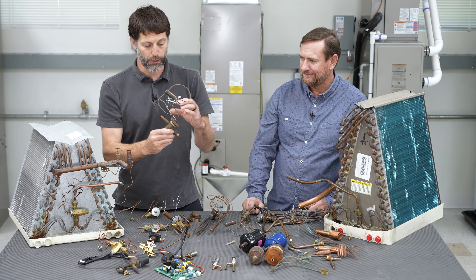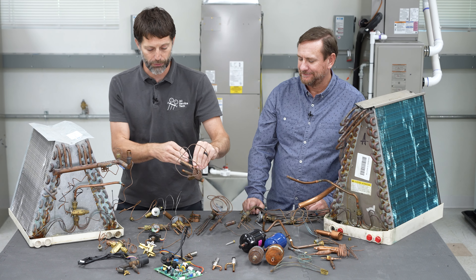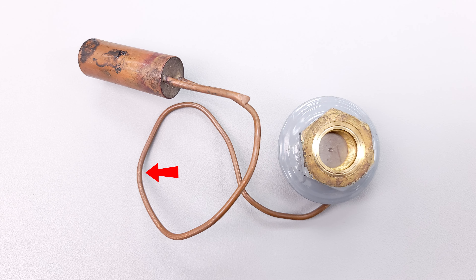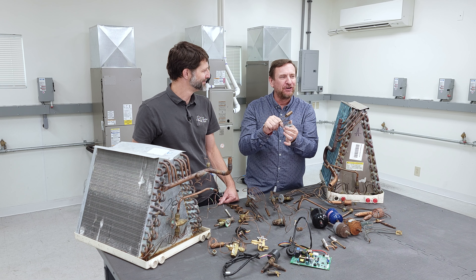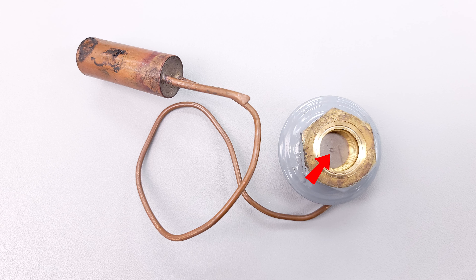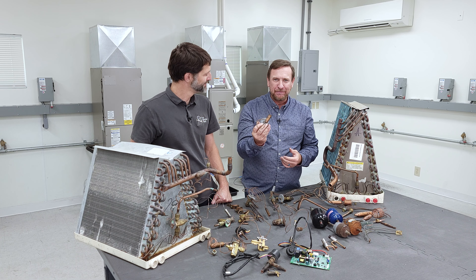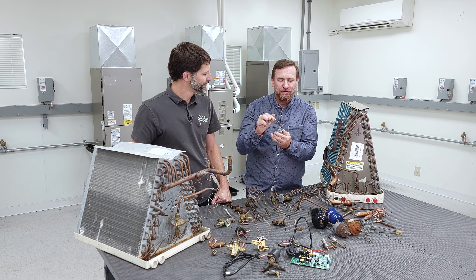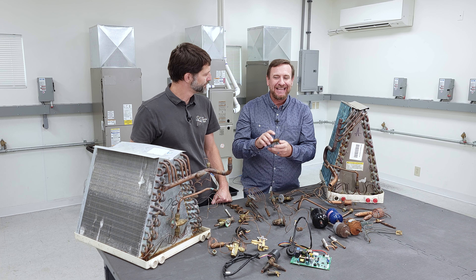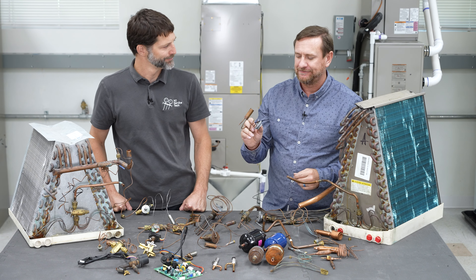If you lose the refrigerant charge in the TXV head, it won't be able to open the internal pathway against the spring pressure and external equalization pressure. The bulb charge is separate from the system refrigerant — if you cut that line right now you'd hear a little refrigerant come out because it's its own enclosed system. As the sensing bulb temperature goes up, the pressure goes up and pushes on a small diaphragm; as temperature goes down, the pressure drops and the spring pushes the diaphragm back. It's a very simple process using temperature and pressure with its own charge. Make sure these lines aren't rubbing against anything — if the line wears through and you lose the bulb charge, it cannot control superheat, but that is not a system refrigerant leak — they are separate cycles.